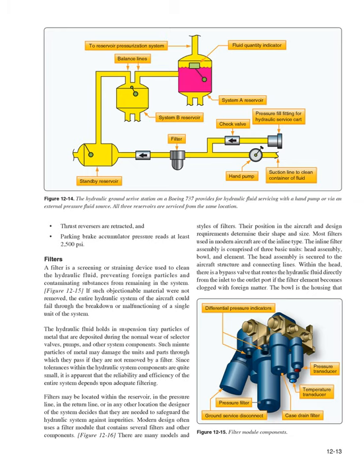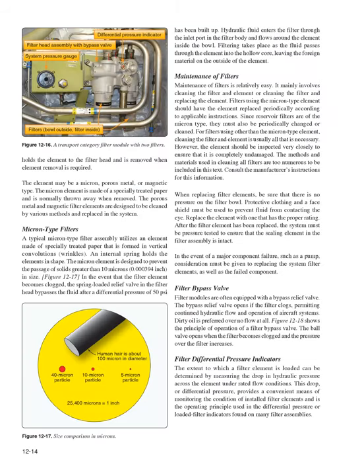Within the head, there is a bypass valve that routes the hydraulic fluid directly from the inlet to the outlet port if the filter element becomes clogged with foreign matter. The bowl is the housing that holds the element to the filter head and is removed when element removal is required. The element may be a micron, porous metal, or magnetic type. The micron element is made of a specially treated paper and is normally thrown away when removed. The porous metal and magnetic filter elements are designed to be cleaned by various methods and replaced in the system.